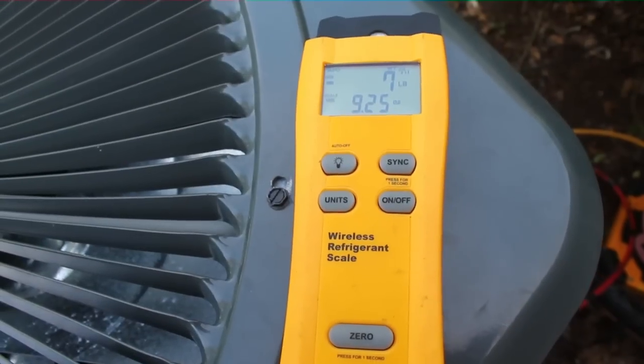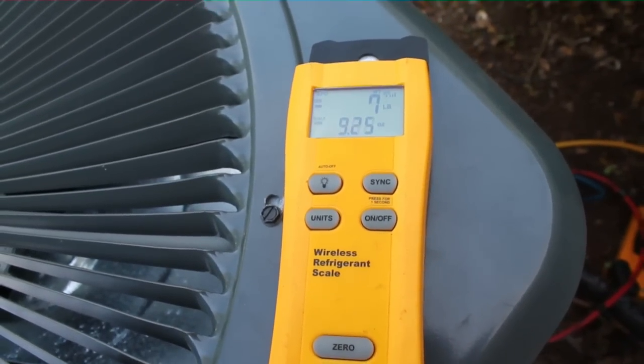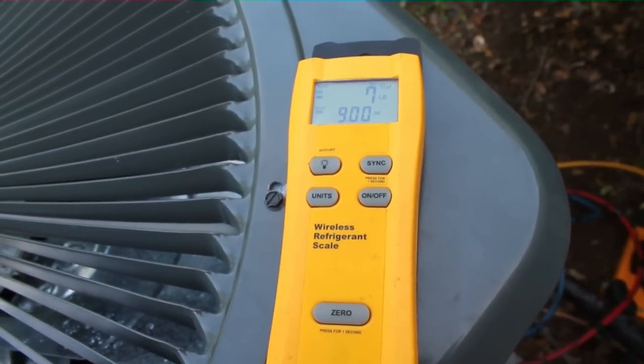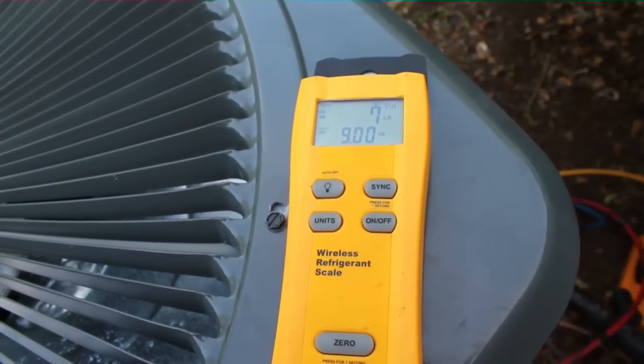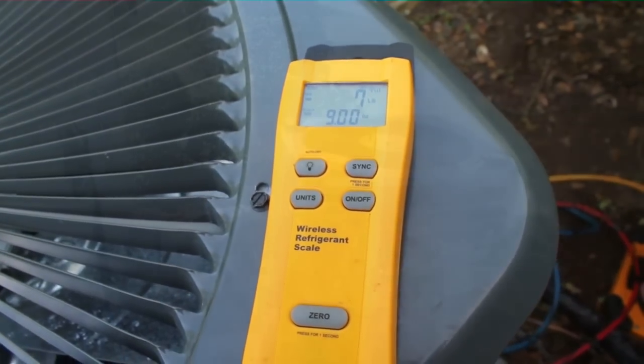We have about 7.5 pounds in there. That's all it'll take. It was going real slow, so I'm going to start the system up, let it run. Put the rest of the charge in there, and we'll fine-tune the subcooling, check our superheat, and see how we're doing.